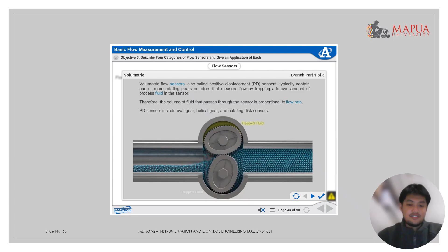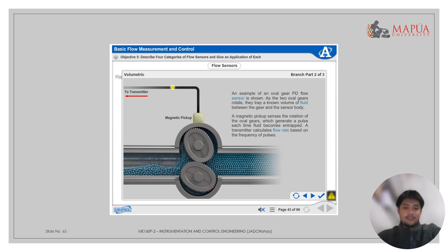Here is the process. An example of an oval gear flow sensor is shown. As the two oval gears rotate, they trap a known volume of fluid between the gear and the sensor body. A magnetic pickup senses the rotation of the oval gears, which generate a pulse each time fluid becomes entrapped. A transmitter calculates flow rate based on the frequency of pulses.